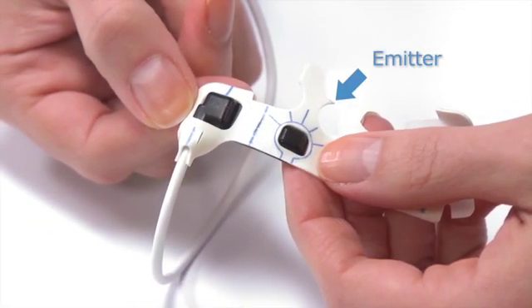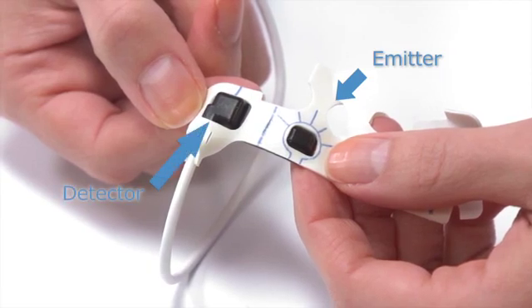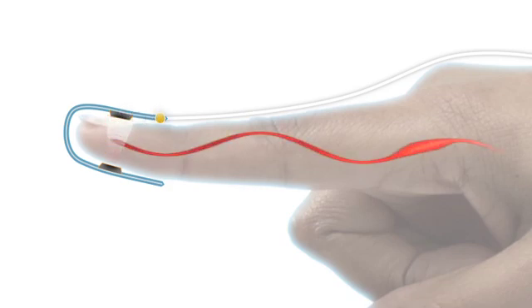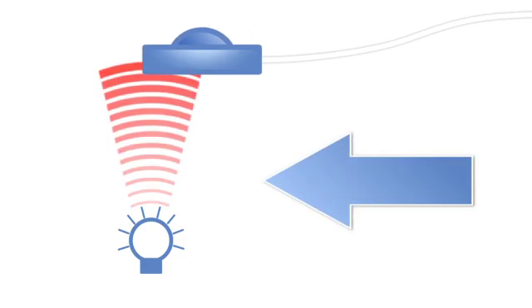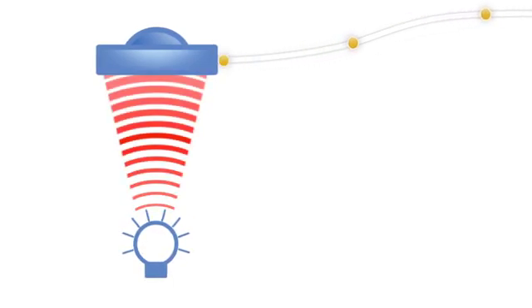Each sensor has an emitter that projects a tuned light wave pattern through the arterial blood flowing in the finger and a detector which receives that light. The heartbeat creates a signal detectable throughout the arteries. This signal is detected by the light waves and used for both measuring pulse rate and oxygen saturation in the arterial blood. The emitter and detector must be directly facing each other and secured to provide accurate measurement. The emitter should rest directly across from the detector.